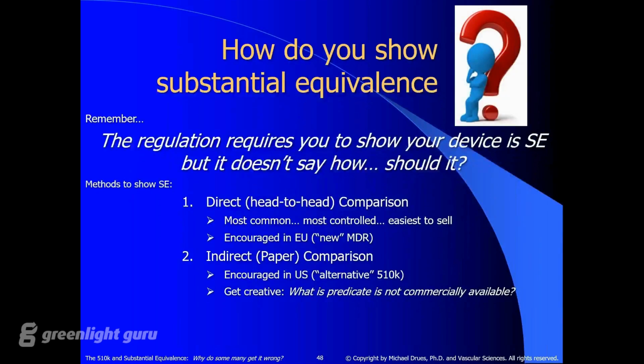And a paper comparison, basically what we do is we compare on paper our results to what we find for our predicate from the literature or from subject matter experts or some other way. In other words, we don't collect the data ourselves. And this is an opportunity to get quite creative. I've been involved in several medical devices where the predicate is no longer commercially available, but there is still an active 510K. So we could not do a head-to-head comparison even if we wanted to, because we cannot physically get the device. And yet we still can bring it onto the market as a 510K if we do it in this indirect or paper comparison way.